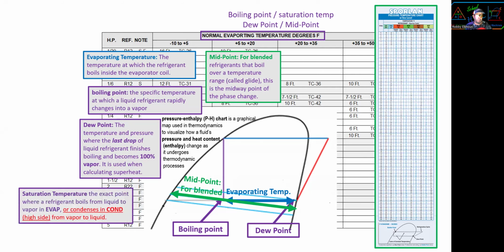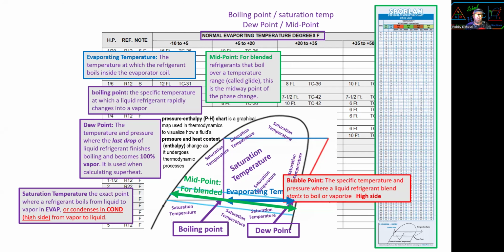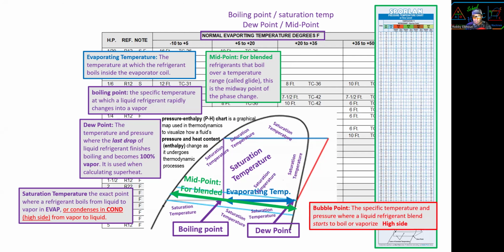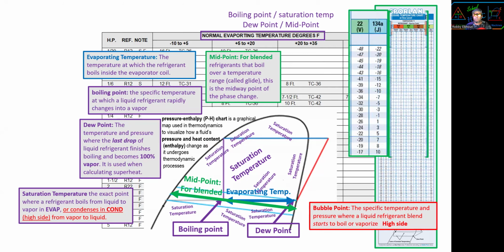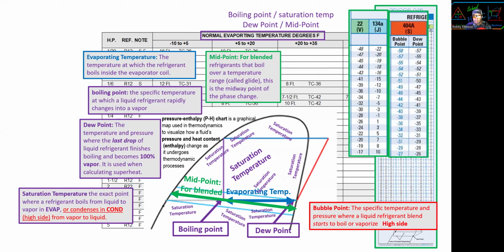Now, saturation temperature is the exact point where the refrigerant boils from liquid to vapor in the evaporator, or in the condenser, the high side, from vapor to liquid. They're both called saturation. That's why I don't like to use that word, too confusing. Let's just use boiling point for the low side, condensing temperature for the high side. Saturation is for both, so let's just not use it at all. But saturation temperature is also correct. All right, so that's your saturation temperature. And now the bubble point, that's for the high side.